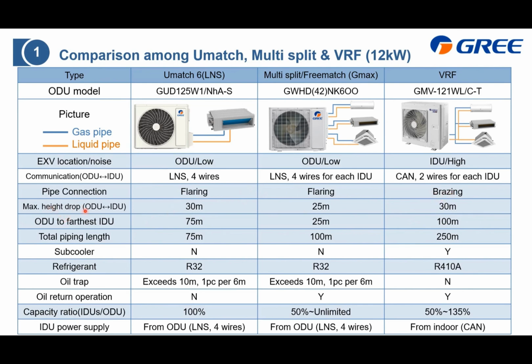And here is the piping information about the height drop from outdoor unit to farthest indoor unit and total piping. I just put it here just for your reference. The reason why this VRF can connect to a longer or further indoor unit is because it has the subcooler. This one. And the purpose of the subcooler is just to increase the subcooling, which makes the refrigerant remain liquid state when it goes to the farthest indoor unit. So that is the reason why it can connect to up to 100 meter.